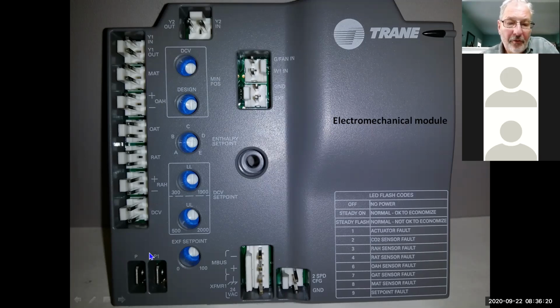Now, if you get into DCV, what you'll see is a plug on this pin right here, demand control ventilation, and it's a CO2 sensor in the space. Basically, when there's nobody in the building or nothing going on, you'll be at minimum position. As you add people to the space and the carbon dioxide levels rise, it will start to modulate the damper open. Okay, so DCV is you set your maximum damper position right here. So if your maximum damper position is 50% for your load for that building, that's where you set it here.